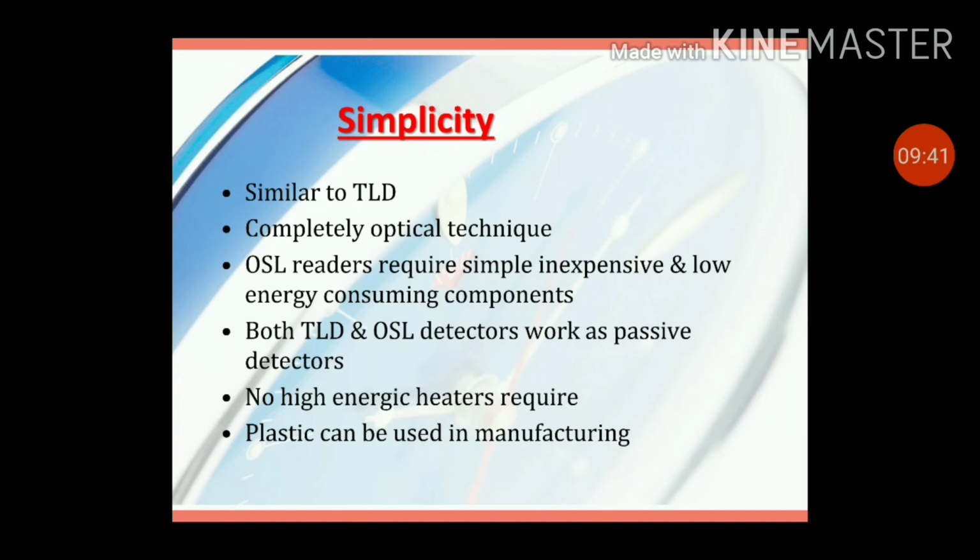Both TLD and OSL detectors work as passive detectors. They will tell the reading later on. So no high energy heaters are required in this technology, and we can even use plastic in manufacturing. OSLD needs simple instrumentation and components that are easy to integrate. OSLD components are the dosimeter, laser or LEDs, light emitting diodes. OSL requires a sensitive light detector that is called a photomultiplier tube.